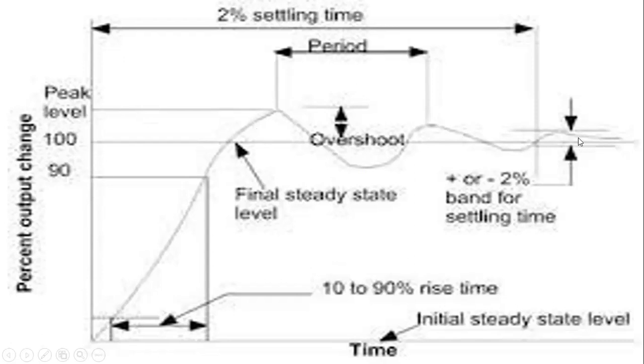The settling band is defined as plus or minus 2% of the final value, and the total time to settle within this band is called the 2% settling time — meaning the time required for the instrument output to settle down to the given input value, in this case 100°C (100% output change).